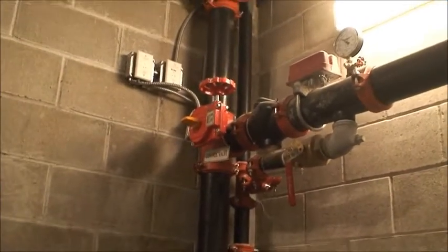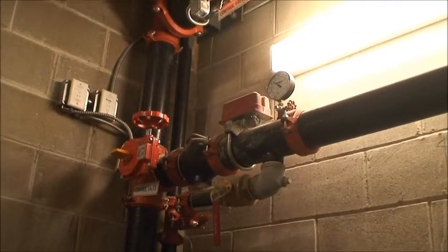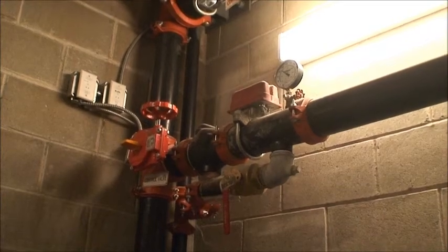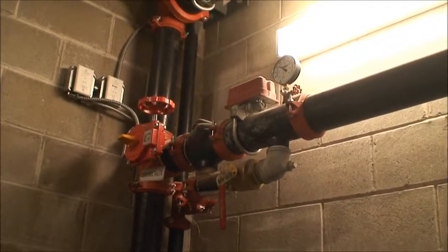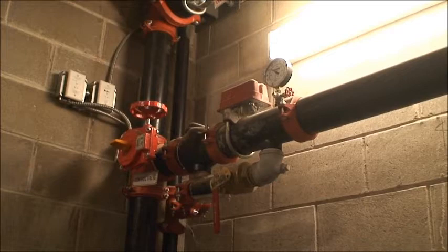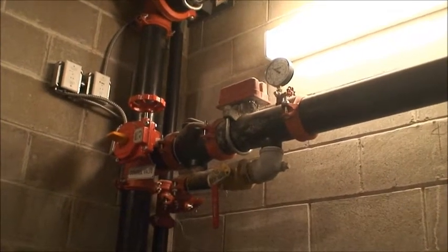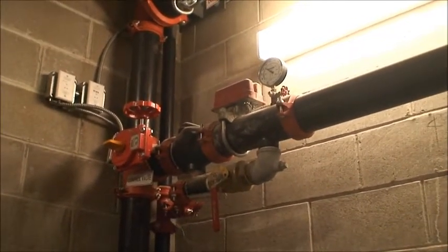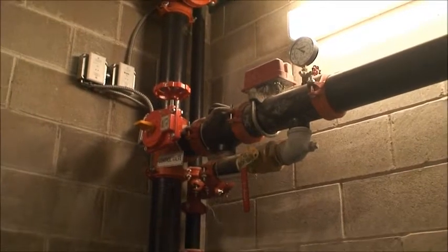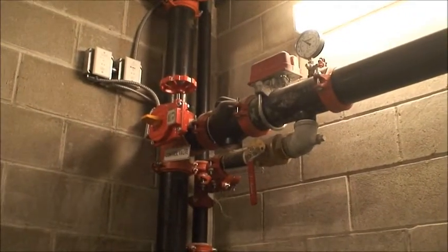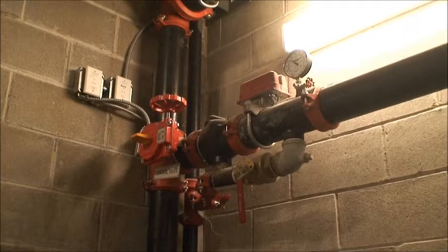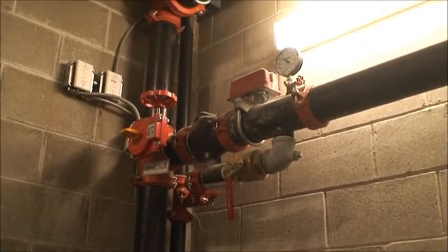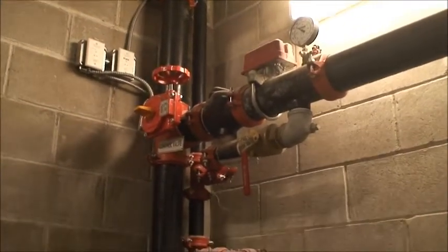That's a good question though, because I'm going to have to do something with that. That should be locked, because if somebody was to hammer that, or even if someone's moving up the stairs and they bump it, it could possibly flow water. It takes 45 seconds before it'll empty, right? Once it really flows, if it is fully opened, you're going to get an alarm. Okay. Yeah. And can you...